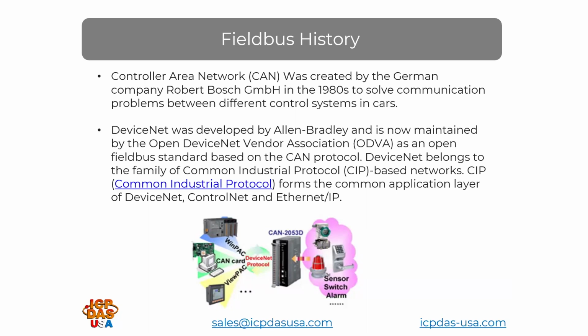DeviceNet was developed by Allen-Bradley and is now maintained by the Open DeviceNet Vendor Association, or ODVA, as an open Fieldbus standard based on the CAN protocol. DeviceNet belongs to the family of Common Industrial Protocol, or CIP-based networks. CIP forms the common application layer of these 3 industrial networks: DeviceNet, ControlNet, EtherNet/IP. DeviceNet is an object-oriented bus system and operates according to the producer-consumer method. DeviceNet devices can be client, master, or server-slave, or both. Clients and servers can be producer or consumer, or both.